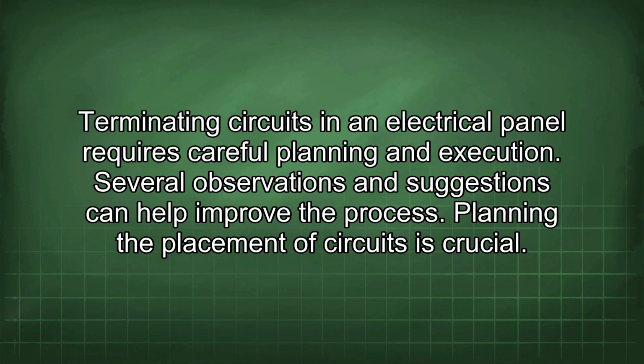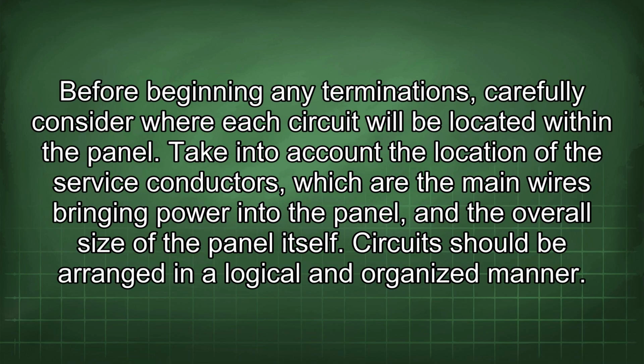Terminating circuits in an electrical panel requires careful planning and execution. Several observations and suggestions can help improve the process. Planning the placement of circuits is crucial. Before beginning any terminations, carefully consider where each circuit will be located within the panel. Take into account the location of the service conductors, which are the main wires bringing power into the panel, and the overall size of the panel itself.